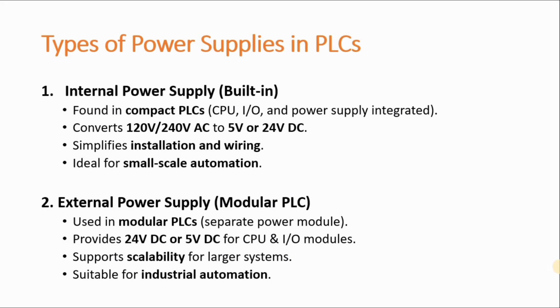Now let's see the types of power supplies in PLCs. There are two main types: internal and external power supply. Internal power supplies are found in compact PLCs, a type of PLC where the CPU, input-output modules, and power supply are integrated into a single unit. The internal power supply converts 120 or 240 volt AC into 5 volt or 24 volt DC. It simplifies installation, reduces wiring complexity, and is best suited for small scale automation systems.